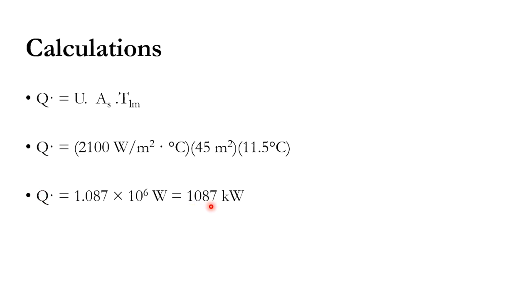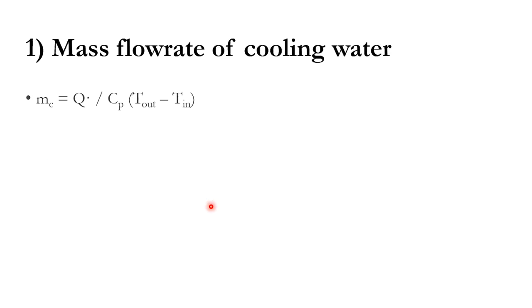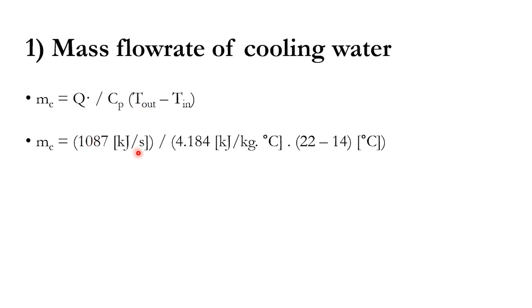To find the mass flow rate of cooling water, we use Q = m·Cp·ΔT, so m = Q / (Cp · ΔT) = 1087 kJ/s divided by 4.184 kJ/kg°C and (22 − 14)°C. The units cancel and we get 32.5 kg/s of cooling water required.